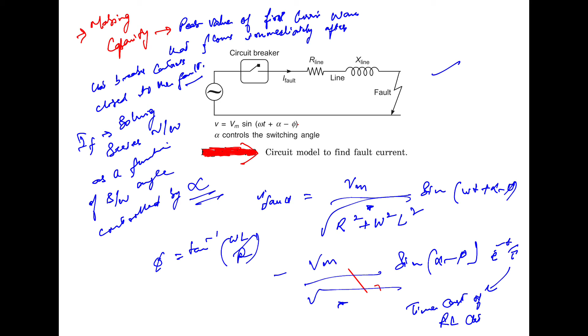Now, from this what we observe, it actually shows the peak value of the transient current. This shows the peak value of the transient current a short time after switching the fault, and it can reach a value double the peak value of the steady state fault. If the peak, which is 100 in this case, you will see that it will reach double, because initially the steady state value was 100. Such a high value of 200% of the fault current is to be made by the circuit breaker without any damage to the contact, that we have to take into consideration.